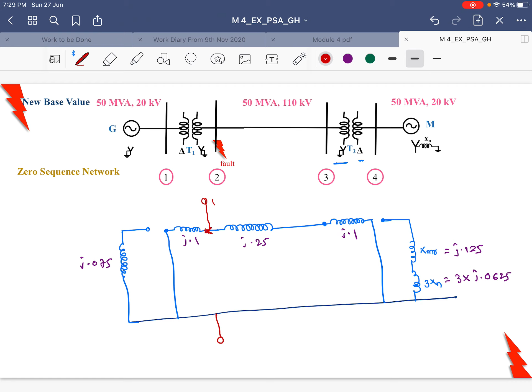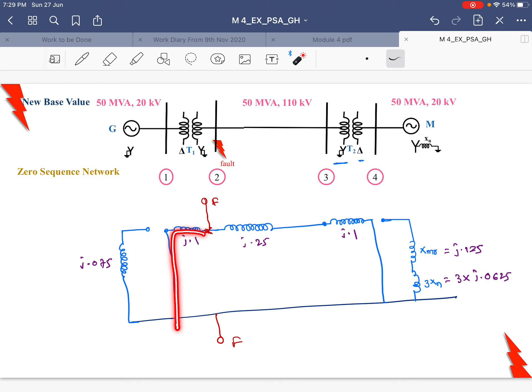The fault is occurring soon after the transformer here. That is, you have to look into the Thevenin's equivalent seen from these 2 points, F and F dash. If you look carefully, on the left hand side you have got only one reactance to the ground. This is open here, therefore this will not come into picture. Then on the right hand side, only these 2 reactances come into picture. This is once again isolated.